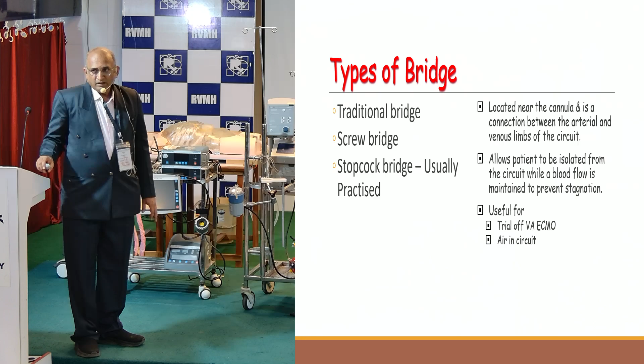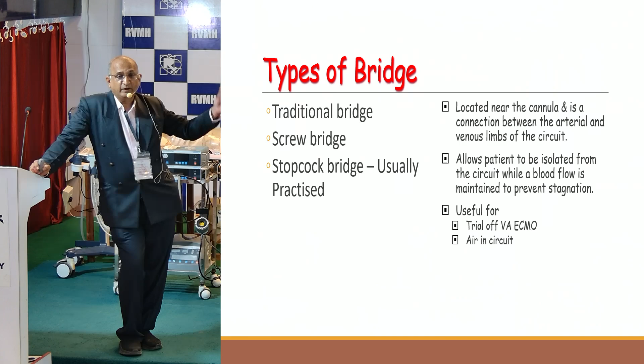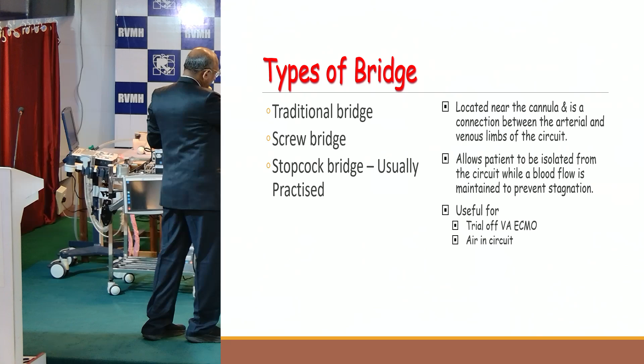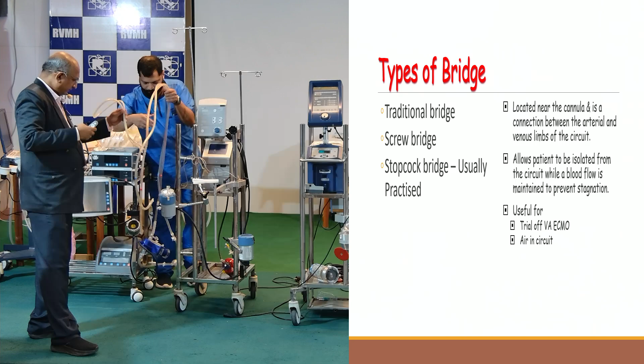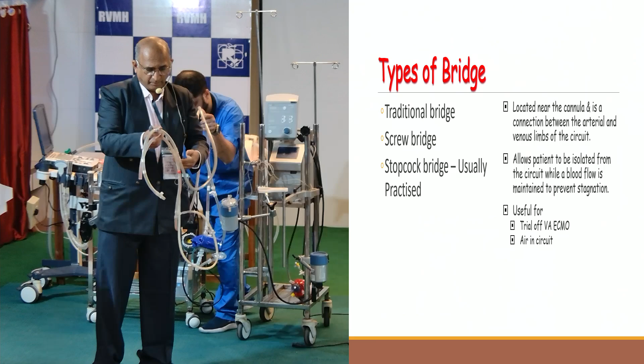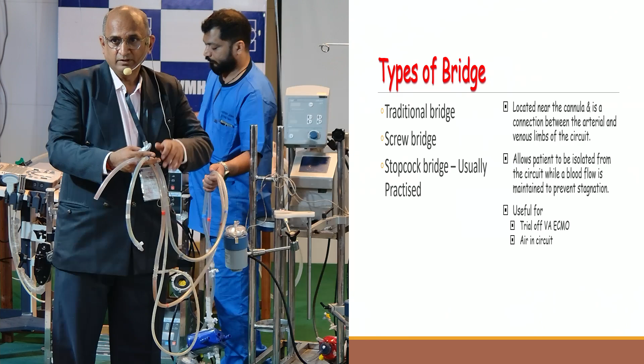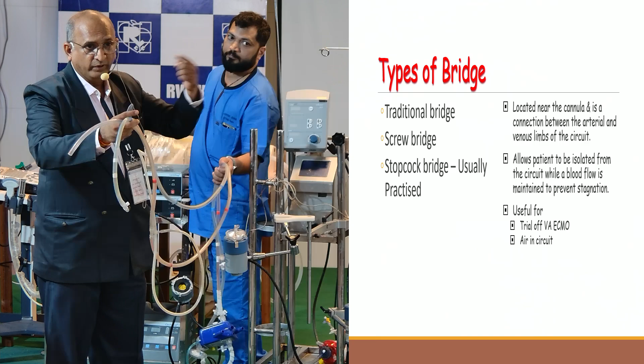See, there is no routine use of the bridge. In fact, it is used only when you want to separate the patient from the circuit. When you want to separate both of them, yes, you require a bridge. So this is the way we put a bridge. This is toward the patient. We keep the bridge as close to the patient as possible. Now when I clamp this, nothing is going to the patient. And when I open this bridge, the blood is moving in the circuit and nothing goes to the patient. This is the bridge.